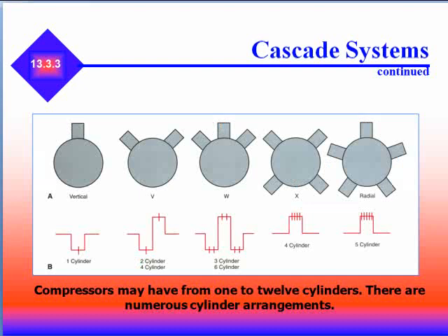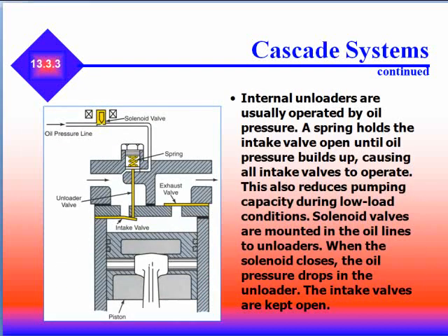Compressors may have from 1 to 12 cylinders with numerous cylinder arrangements. In cascade systems, internal unloaders are usually operated by spring and oil pressure. A spring holds the intake valve open until oil pressure builds up, causing all intake valves to operate — this also reduces pumping capacity during low load conditions. Solenoid valves are mounted in the oil lines to unloaders.